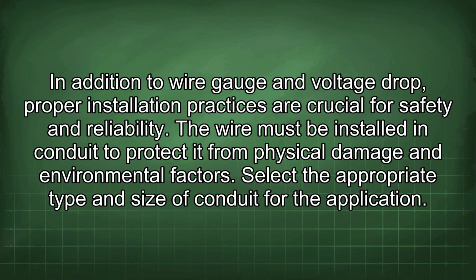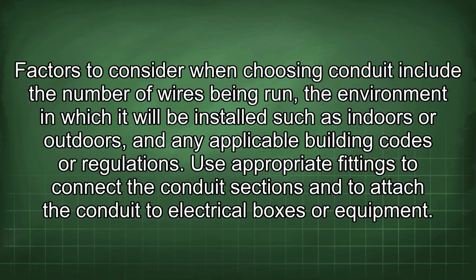In addition to wire gauge and voltage drop, proper installation practices are crucial for safety and reliability. The wire must be installed in conduit to protect it from physical damage and environmental factors. Select the appropriate type and size of conduit for the application. Factors to consider when choosing conduit include the number of wires being run, the environment in which it will be installed, such as indoors or outdoors, and any applicable building codes or regulations.